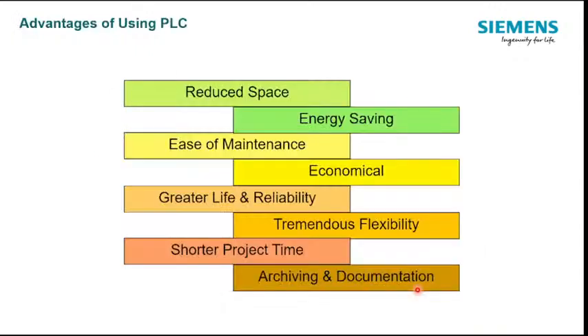When we use PLC, we save on space, we save energy. It's easy for maintenance because during troubleshooting, we are able to find out where the root cause is within a few clicks. So it will save your time during your breakdown, and it will help us to resume your production as early as possible. It's economical when compared to the hardware relay logic control. It gives long life and is reliable.